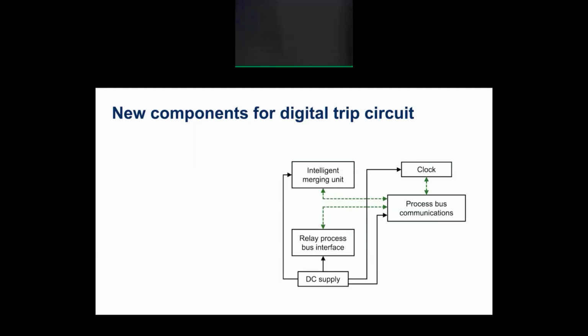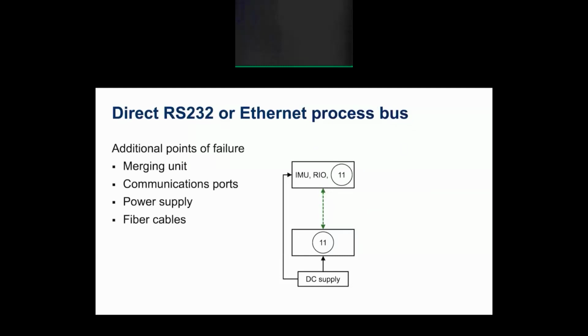So let's look at the new components of a digital trip circuit. The new components must meet the requirements of the harsh environment among the primary equipment, and these include process bus interfaces on the relay and new merging units, which are direct wired to the process and do the analog to digital conversion. And we need a process bus communications network, and we often need a clock. So let's look at a couple of installation methods.